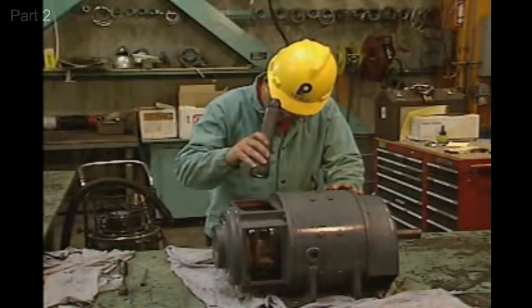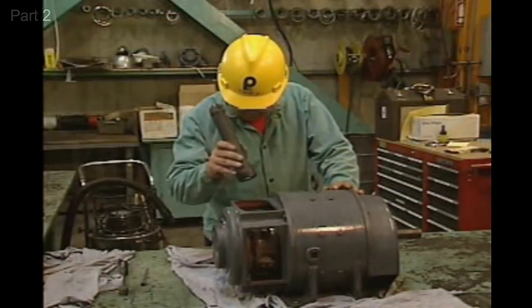Then the area between the commutator segments can be cleaned. This area is likely to collect dust, brush chips, copper flakes, and other particles. A good light makes it possible to check this area visually.